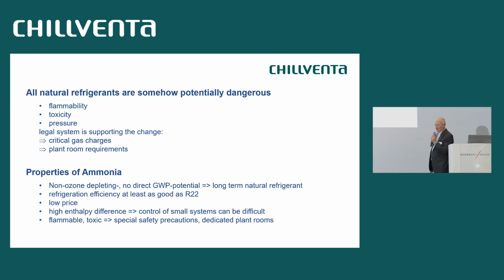The flammability and the toxicity is actually not such a big deal anymore. We have to just follow the safety precautions and the dedicated plant rooms which cannot be entered by other people. A little bit of a problem can be the oil miscibility, especially for contractors who have to convert from freon and these refrigerants where the oil is on the top to ammonia where the oil is on the bottom.